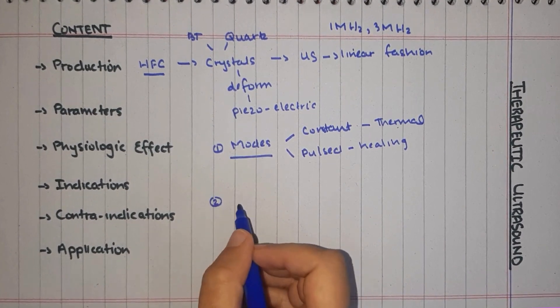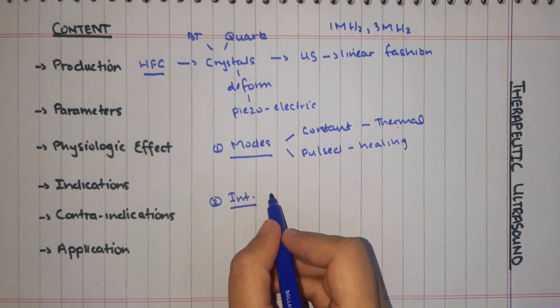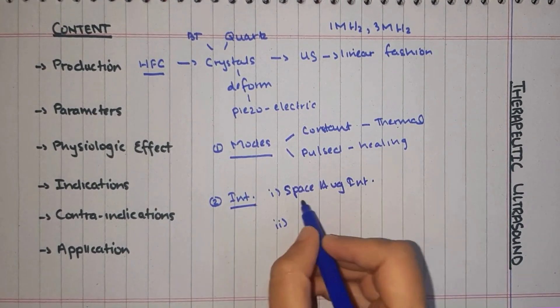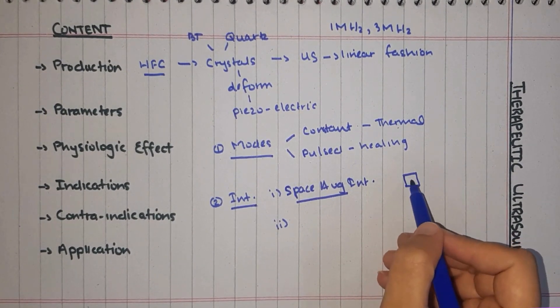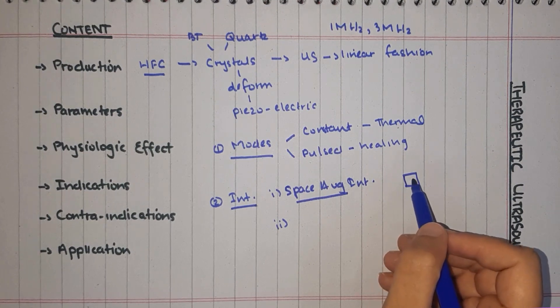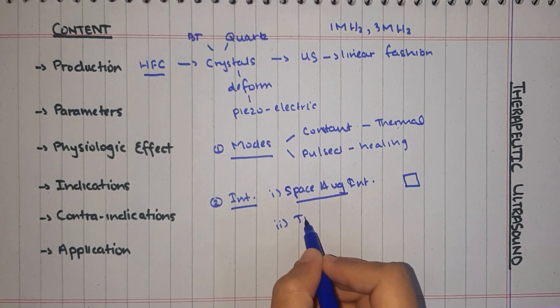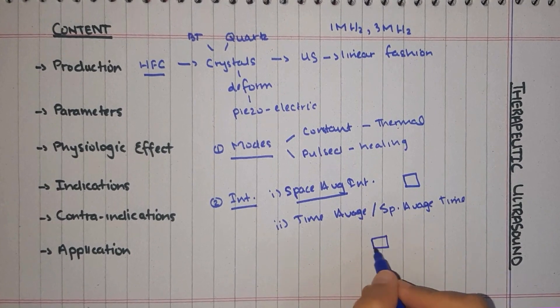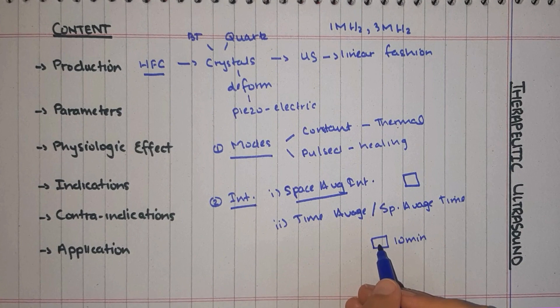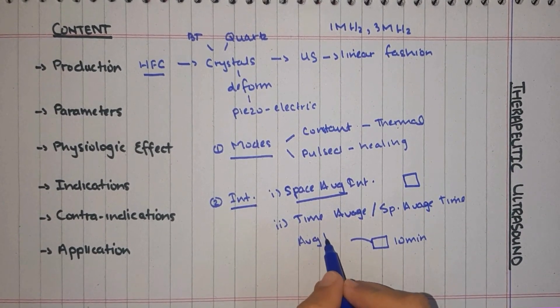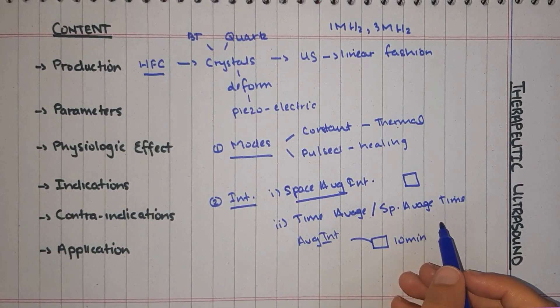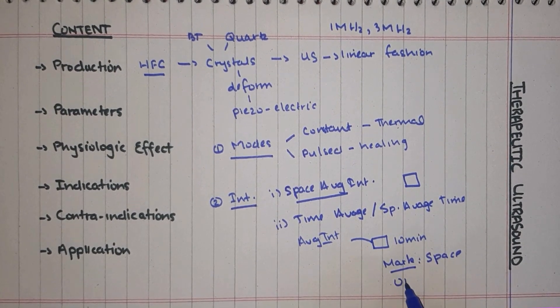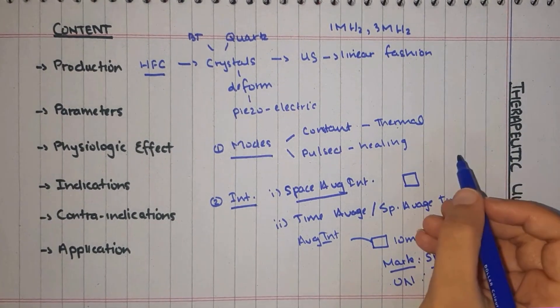The second parameter is intensity. There are two important terms to understand: space average intensity and time average intensity. Space average refers to the specific treatment area, while time average refers to the average intensity over the treatment session — for example, a 10-minute session. Another important concept here is the mark-space ratio, which is used in pulse mode.